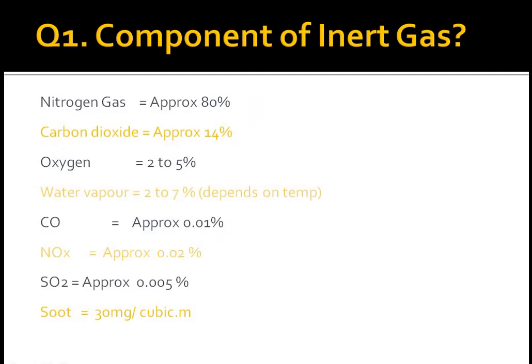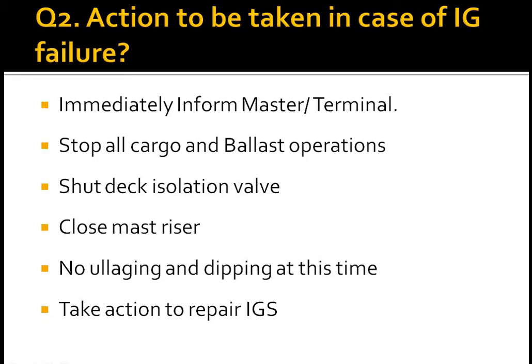First question: components of inert gas. Nitrogen approximately 80%, carbon dioxide approximately 14%, oxygen 2 to 5%, water vapor 2 to 7% depending on temperature, carbon monoxide approximately 0.01%, nitrogen oxide approximately 0.02%, and soot 30 mg per cubic meter.